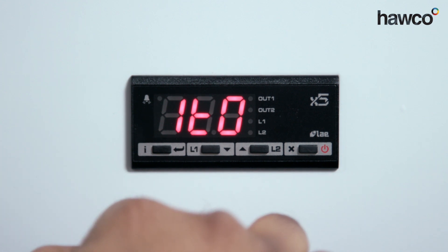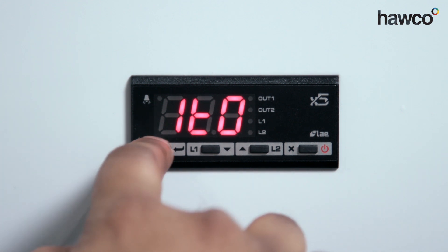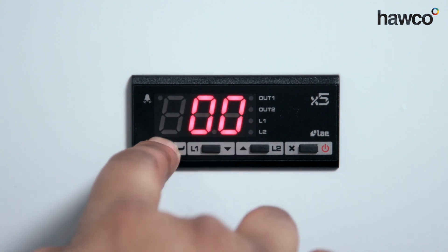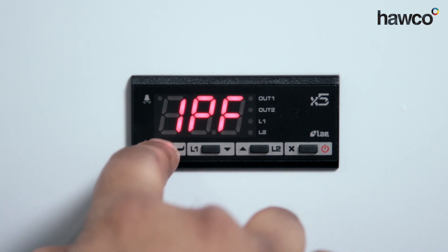The next one is 1TO for minimum off time. In this scenario, we're going to change this down to zero. 1T1 is minimum on time, again, down to zero. The next one's going to be 1PF. We're going to have this set to off.